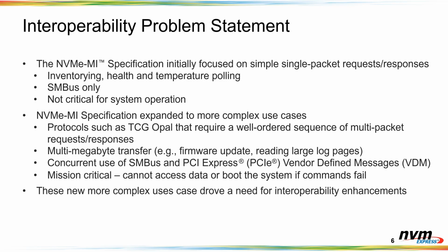The commands are less likely to fail due to their simplicity. But even if they do fail, the impact is not usually catastrophic. If you can't get the current temperature, then the BMC could just ramp up the fans to cover the worst case. And if a health poll command doesn't work, well, the typical case is the drive has failed, and so there's no impact. But even in the event the drive is failed, the failure could still be detected and handled in band.